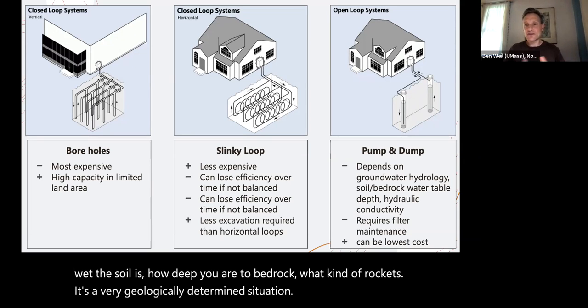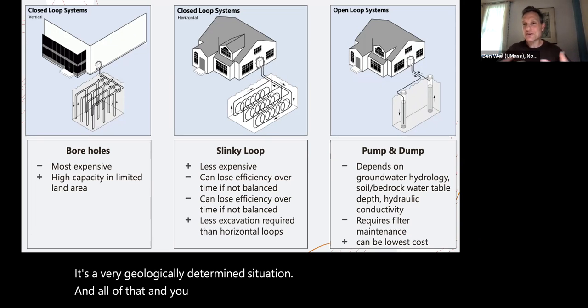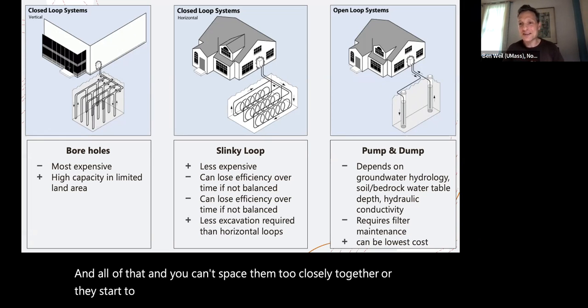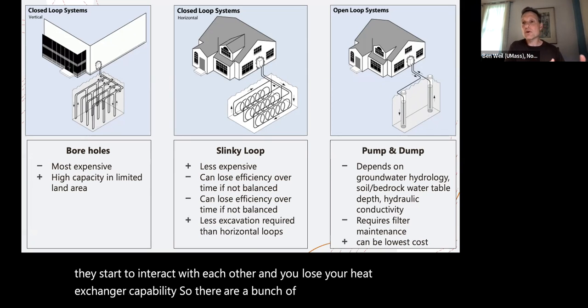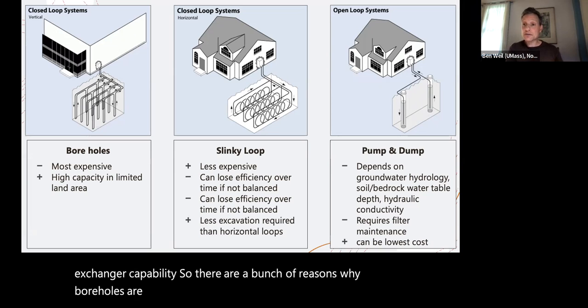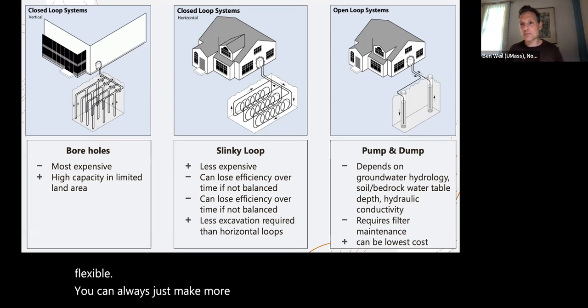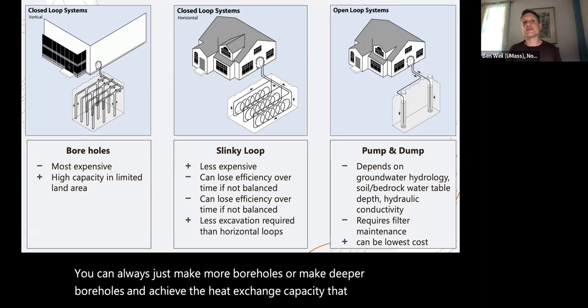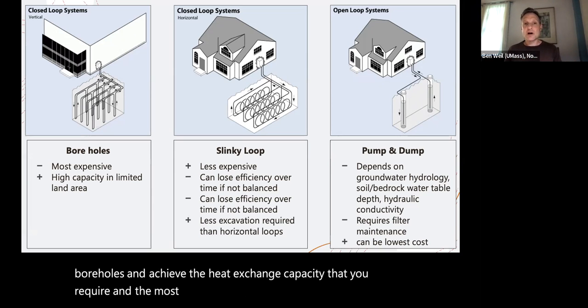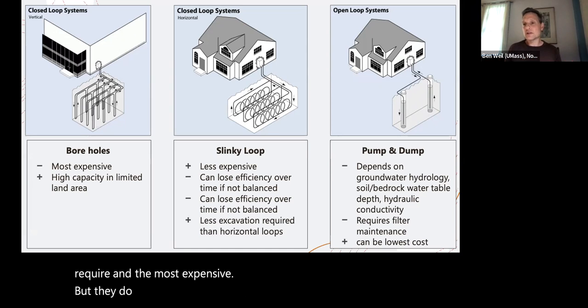And you can't space them too closely together or they start to interact with each other and you lose your heat exchanger capability. So there are a bunch of reasons why boreholes are both very common because they're the most flexible. You can always just make more boreholes or make deeper boreholes and achieve the heat exchange capacity that you require, and the most expensive. But they do better when you have a limited land area.